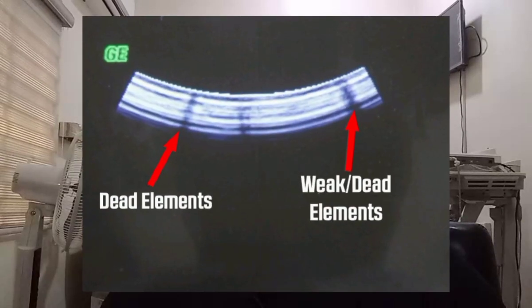Since it can be electronically focused, there are no moving parts to wear out. The disadvantage is that a large acoustic footprint requires a large contact area with the skin, and they cannot be used when an acoustic window is small. When an element malfunctions, a single line of image data extending downward will be lost; the remainder of the image is essentially unaffected. This image of the convex sequential array transducer shows a sketch comparing the linear and convex fields of view.